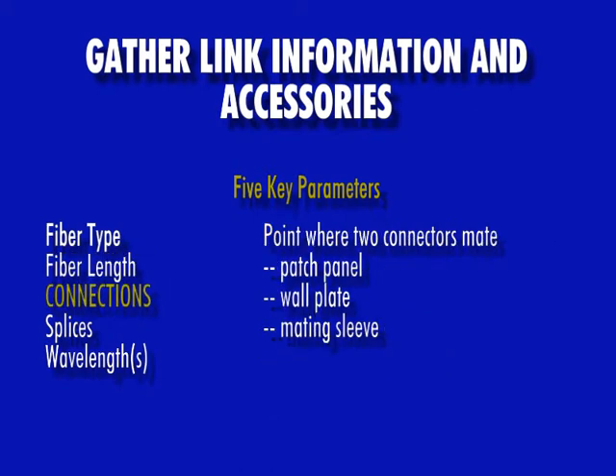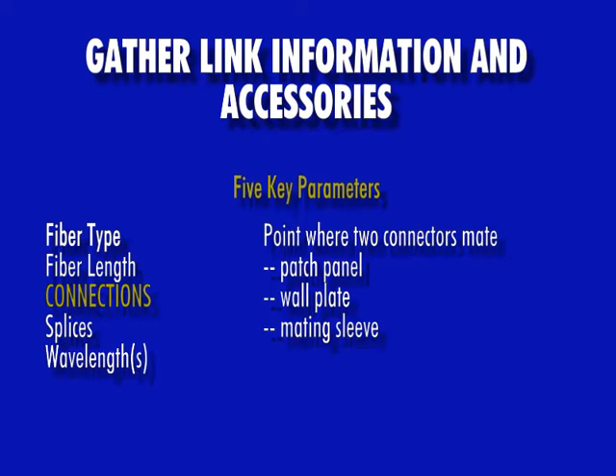Third is number of connections. A connection is the point where two fiber connectors mate together, such as in a patch panel, wall plate, or mating sleeve. Fourth is the number of splices, which can be either fusion or mechanical. For the purpose of calculating a link budget, most cabling standards do not distinguish between fusion and mechanical splices.